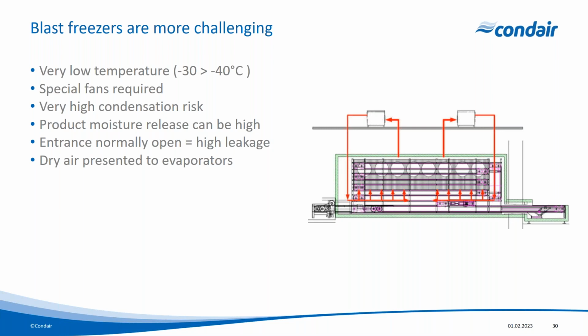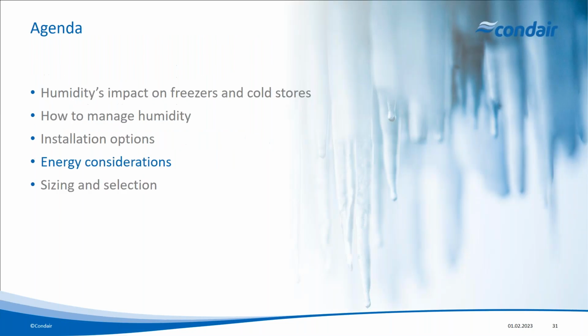So it's more difficult to maintain a low relative humidity or lower relative humidity in a blast freezer because we've got this much bigger difference in temperature, much more turbulence in the air, and those two constantly open in and out ducts. So you can do it by putting a dehumidified air and presenting that straight onto the evaporator. You do get some sublimation there with the ice, but it's much more challenging. So there's some of the ways that we do it.